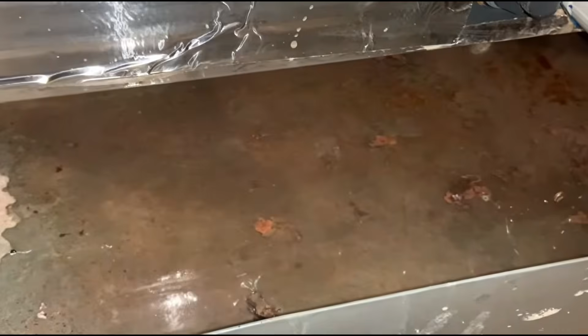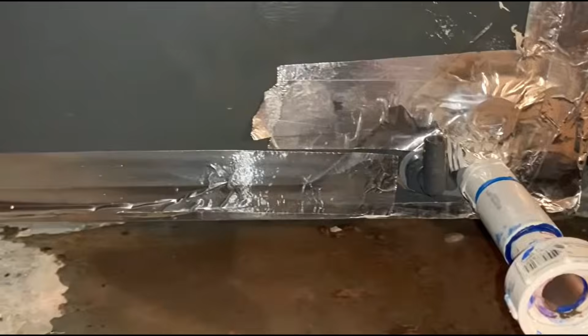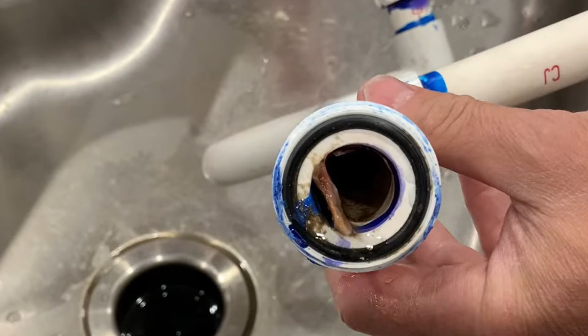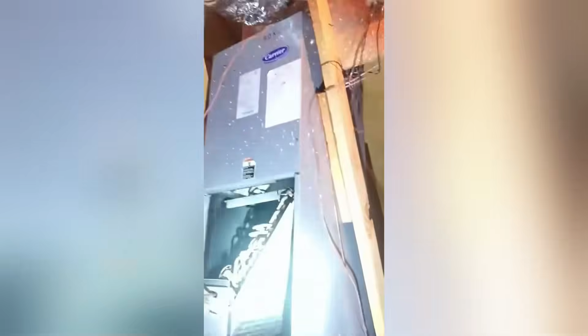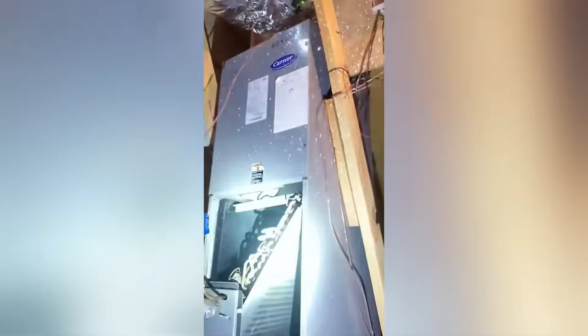3. The clog that shuts your whole system down in July. Your AC pulls gallons of water a day out of the air, and all of it drains through one white plastic pipe. And inside that pipe, it's dark, damp, and warm, so algae and mold grow a slimy film on the wall. The film grabs dust, and eventually the pipe packs solid. When it blocks, a float switch trips and shuts the whole system off on purpose, so the water doesn't back up into your ceiling. That's worth sitting with for a second. The unit was never broken.